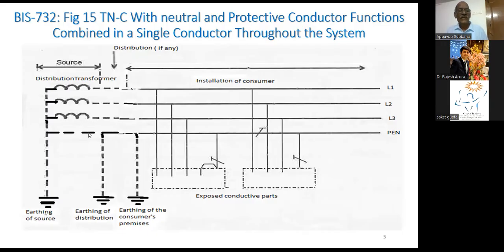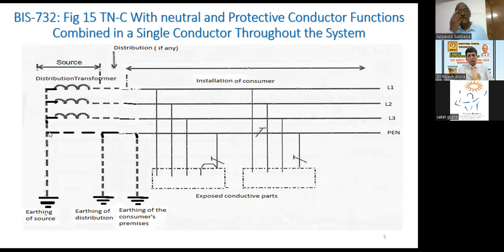That is, the neutral is acting as a protective earthing conductor also, because suppliers have a vast geographical area where they can't provide a separate conductor for earthing exclusively. That's why they are permitted to have a combined conductor for bringing neutral as well as the earth. So here they have to provide multiple earthing along the pole. The CEA regulation says they have to provide multiple earthing up to the consumer premises.